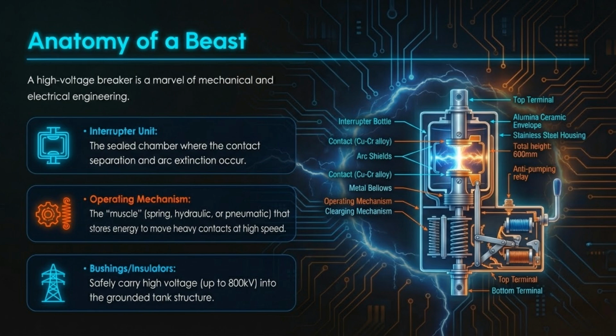The anatomy of this engineering marvel includes the interrupter unit, where the arc is extinguished, and the operating mechanism, which stores energy to quickly separate the contacts. Bushings and insulators safely carry the high voltage into the grounded tank structure.